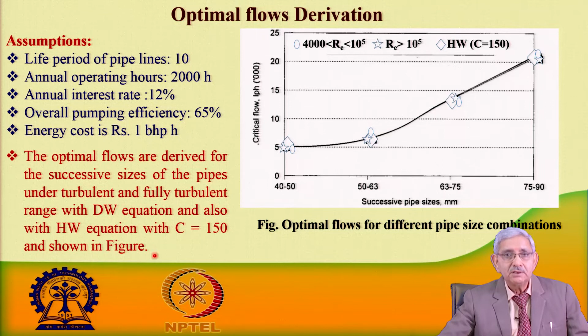When we consider the Darcy-Weisbach equation for the turbulent flow, the optimal flow for the pipe size combination of 40 to 50 millimeter is 5085 liter per hour, and when we consider a larger size pipeline, 75 to 90, we are getting 21,049 liter per hour. Now, these values indicate the flow rates at which the pipe sizes can be changed.